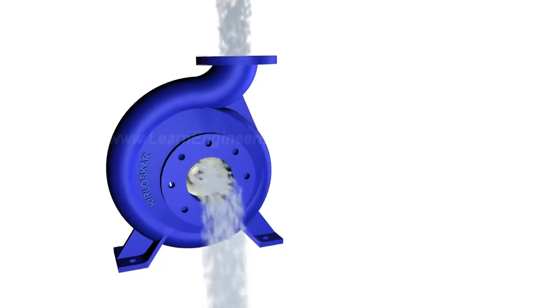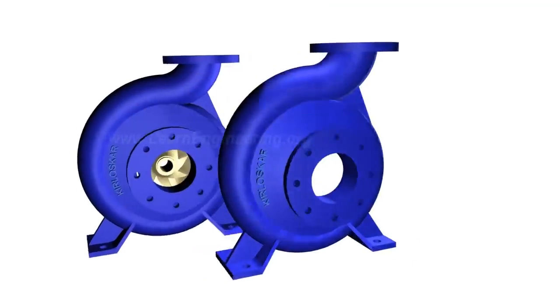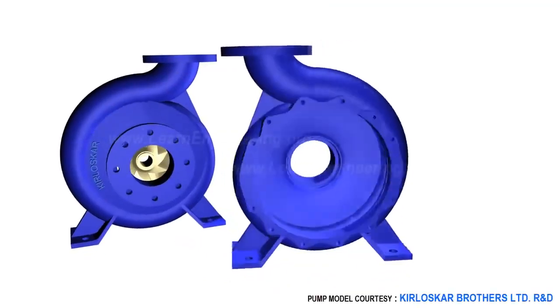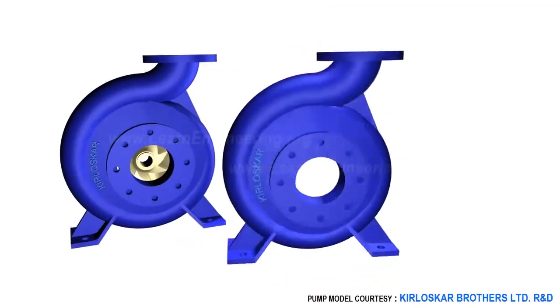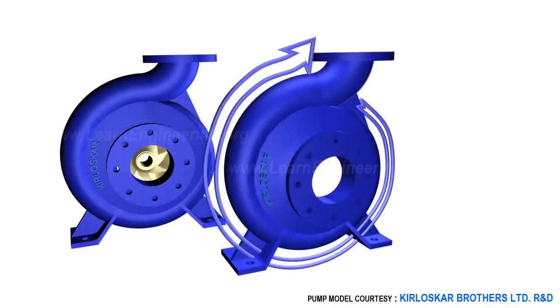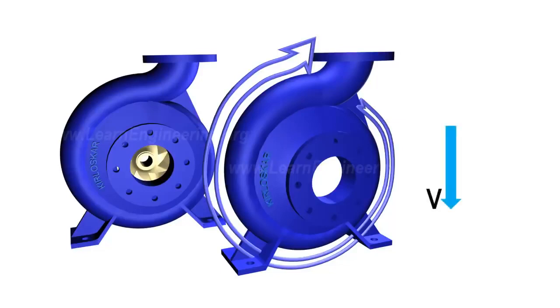Here you can note one specialty of casing - it has got increasing area along the flow direction. Such increasing area will help in accommodating newly added water stream and will also help in reducing exit flow velocity. Reduction in flow velocity will result in increase in static pressure which is required to overcome resistance of pumping system.